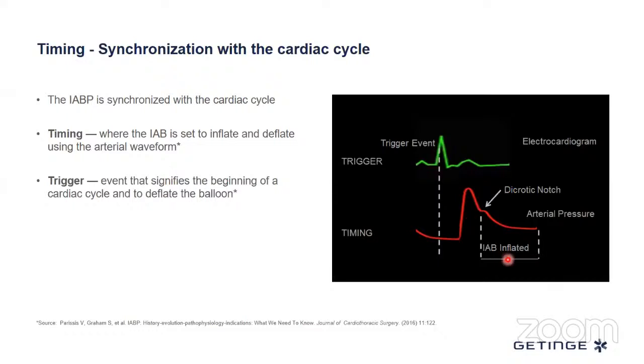The question I get sometimes from clinicians or perfusionists in a hurry to initiate therapy is: I have a patient on the table, he's draped, now I need to start the balloon pump. Can I start a pump without attaching the ECGs? And it is possible. It is not optimal, but it is possible.